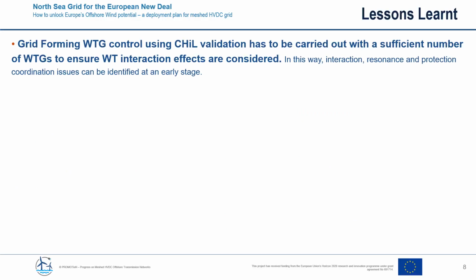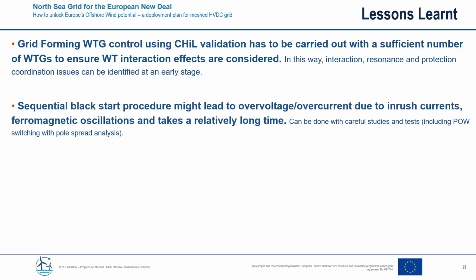The previous results are just a small portion of the tests that we carried out. The main lessons to learn is that the real-time simulation must have a sufficient number of wind turbines, so the resonances and interactions between the wind turbines are identified at a very early stage. Sequential black start is possible, but it might lead to overvoltages and overcurrents, which could trip the wind turbines in some cases, so detailed studies are needed if sequential black start is to be used.